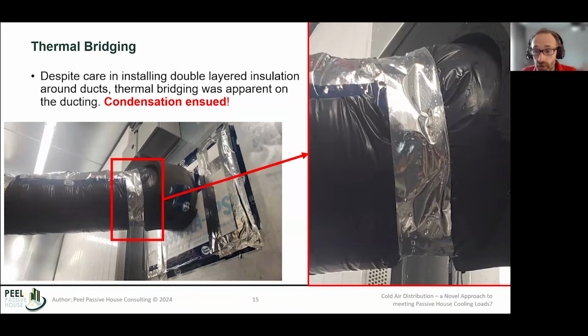Another practical challenge, which will inform implementation in actual buildings, is that despite a decent amount of care wrapping a double layer of insulation around the ducts, we see thermal bridging. It shows up. If there's a weakness with these kinds of conditions, condensation is going to show up with such cold air in the duct. That became readily apparent.